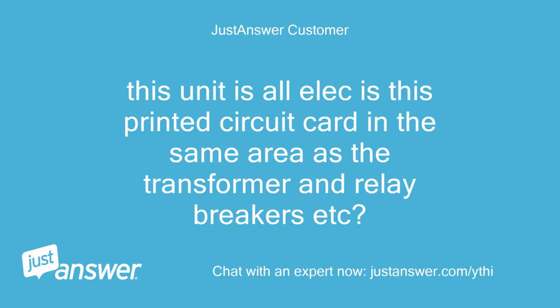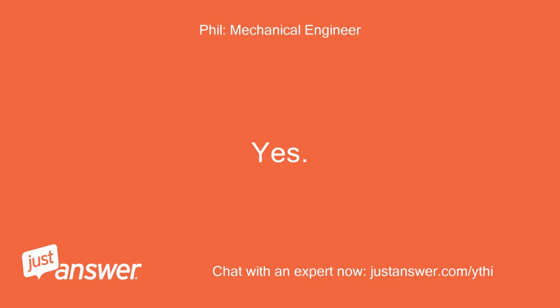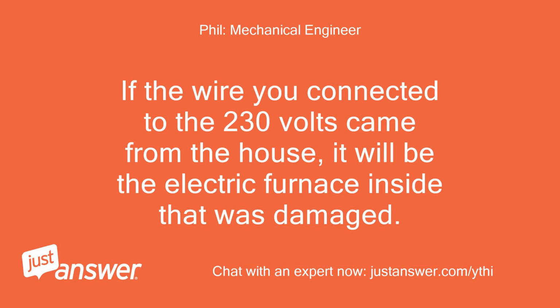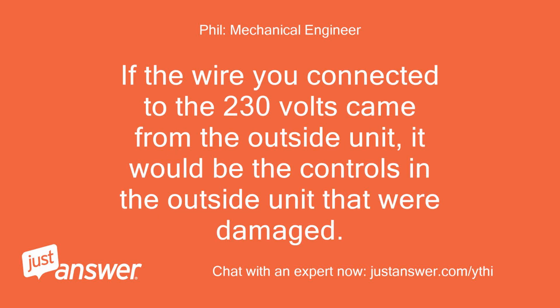This unit is all elec, is this printed circuit card in the same area as the transformer and relay breakers, etc.? Yes. If the wire you connected to the 230 volts came from the house, it will be the electric furnace inside that was damaged. If the wire you connected to the 230 volts came from the outside unit, it would be the controls in the outside unit that were damaged.